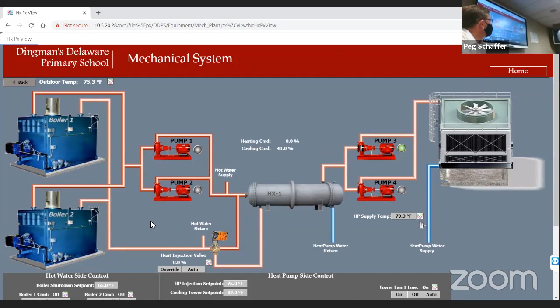If we're in cooling mode and the heat pump is creating cooling, it generates heat into the pipe, and we have to get rid of that somehow. In many cases, people have water source heat pumps where they take the heat and put it down into the ground. In your case, you're putting it out to this cooling tower. During the summer, the cooling tower runs really hard, the fans are running, and we're getting rid of the heat in the building and putting it in the pipe, then blasting it out into the atmosphere. That air is not connected to the ventilation. They're not married — there's a heat exchanger that separates them. The ventilation air is completely separate from any of the other air on this cooling tower.